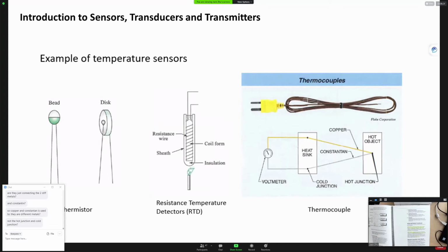So if your ambient temperature here is 30 degrees and your hot junction here is maybe 100 degrees, the difference of 70 degrees will cause a certain voltage here, instead of, if you have 100 degrees here and 0 degrees here, that will be a different voltage generated.